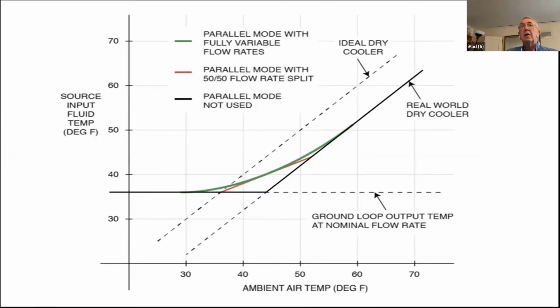So this graph shows three different conditions for the valves and pumps that we were describing earlier. And this shows the example where the building needs to be heated. And if you have an air source heat pump, then what you've got is the 45-degree angle line that's called real world dry cooler there. And that would follow all the way down to the bottom left, which means you're going to have really cold water for the heat pump, even though you're trying to get heat for your building.